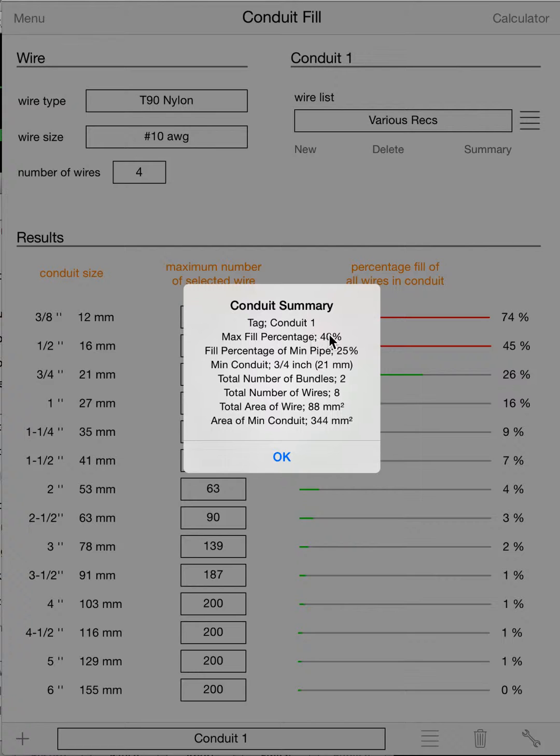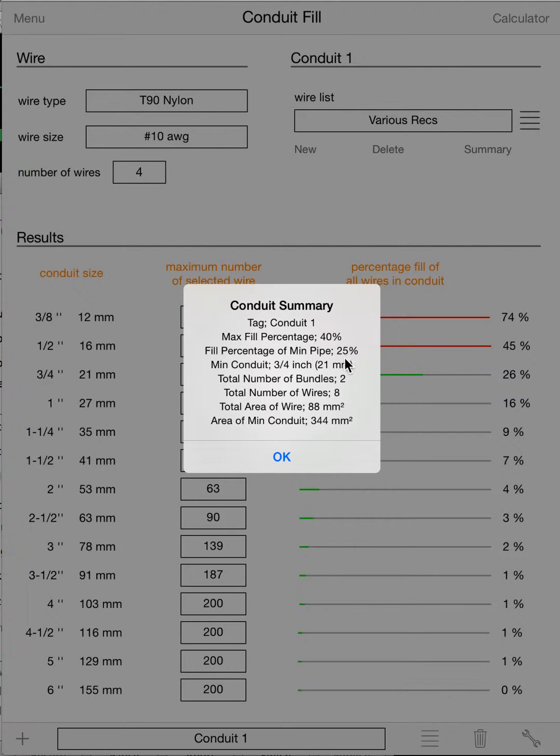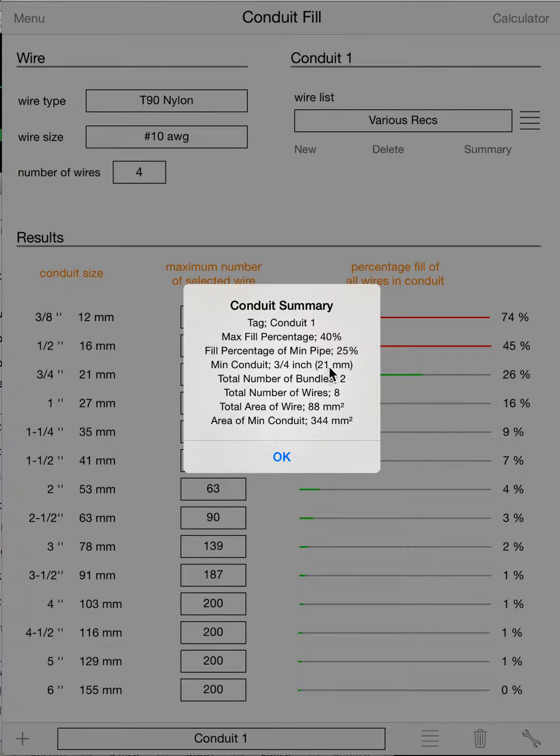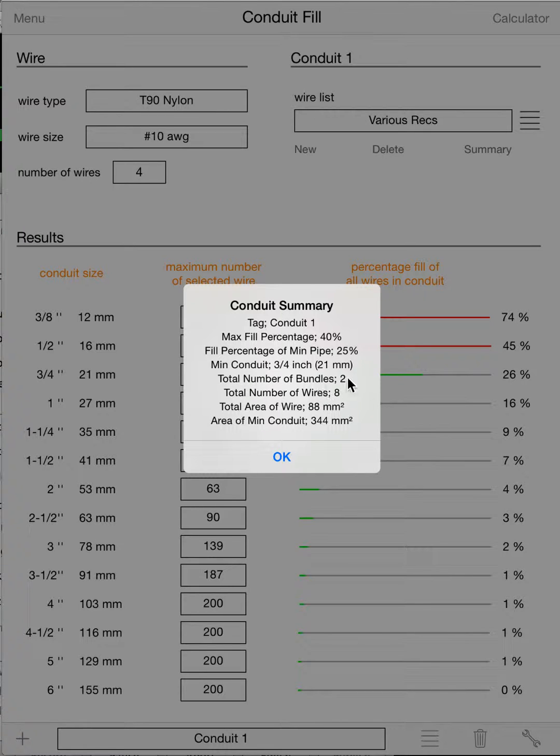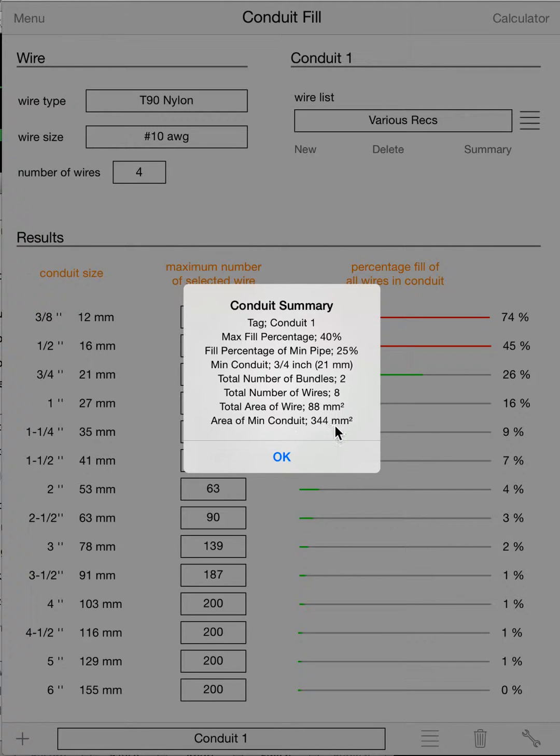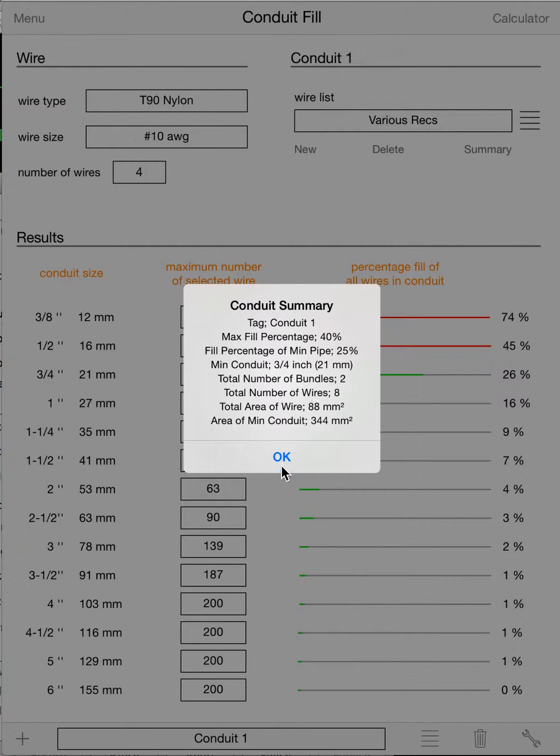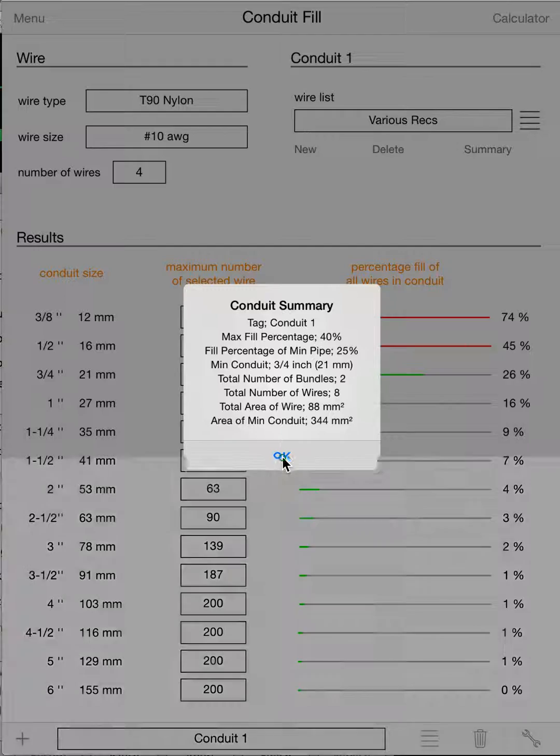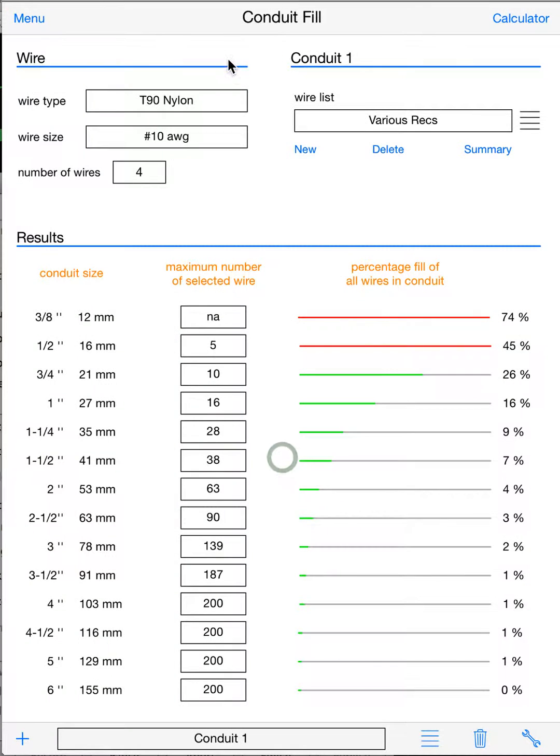It'll give you your maximum fill, which is 40% obviously, give you the fill percentage of the minimum pipe that it's calculated, 25%, it'll give you a minimum conduit, three-quarter inch or 21 millimeters for your metric guys, how many bundles of wire you put in, how many total wires, area of the wire, area of the minimum conduit. So you can kind of double-check the results or whatever you need to do with that information.